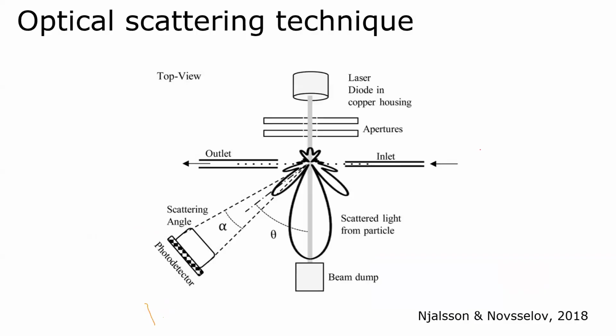Okay, just a very basic schematic of how the optical scattering technique works. You see the inlet and outlet where the particles will be entering. How the particles enter, I can tell you in the next slides. The particles enter the optical chamber, and you have a diode laser, or any laser which emits monochromatic light. These particles in the optical chamber will scatter light, and at a particular scattering angle alpha, you detect this scattered light, and more light means more particles.